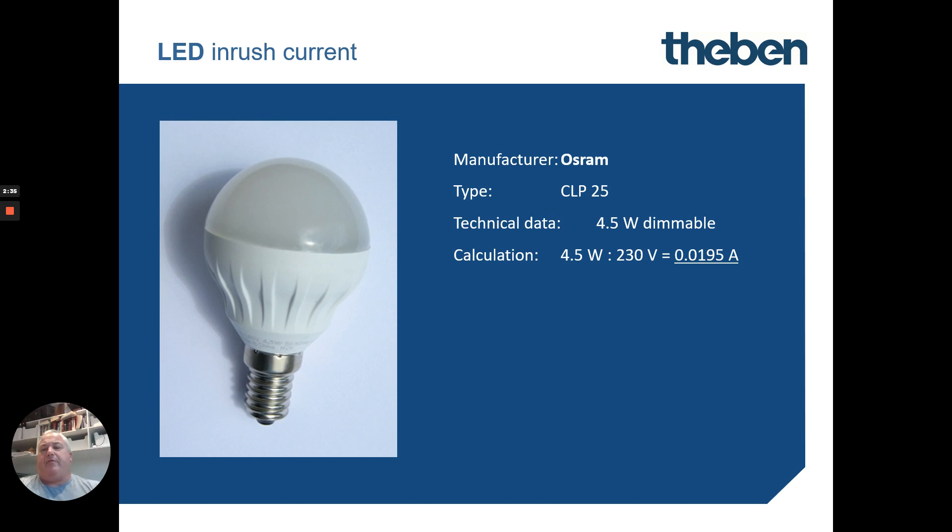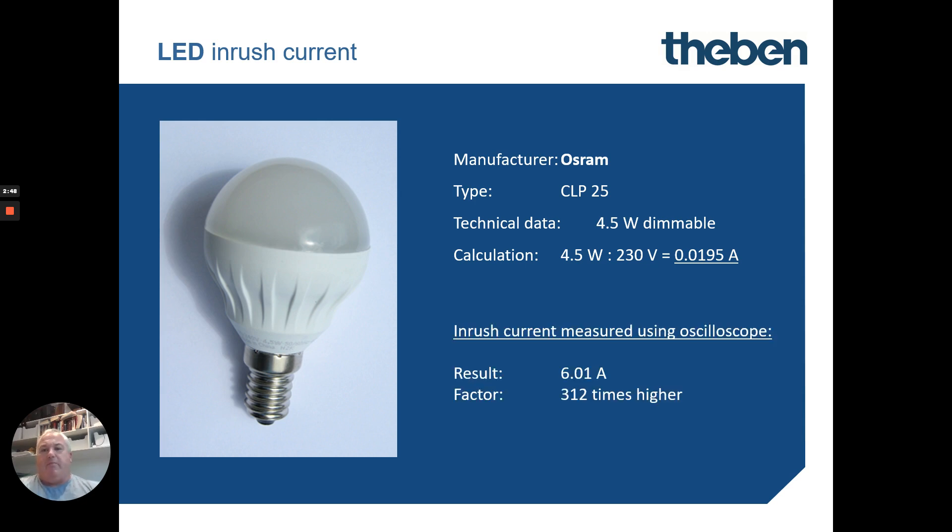First up, a fairly common LED is an Osram LED — it's a 4.5 watt LED drawing a minimal of 0.0195 amps. But when they measured the inrush current for that very split second, it was actually up to 6.01 amps — that's 312 times higher than the original running current.